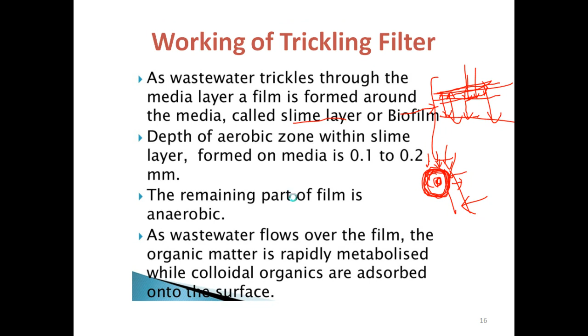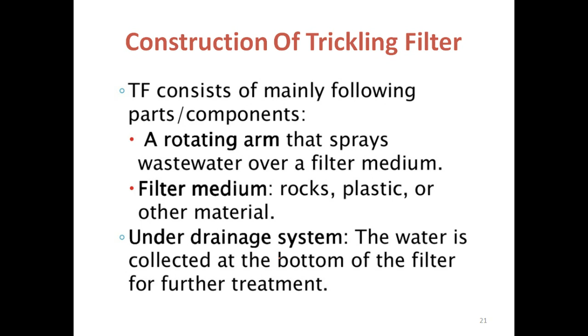One more thing in the working of the trickling filter: before passing water through the trickling filter, it should be passed through the primary sedimentation tank or skimming tank at least. Whatever organic materials in the wastewater can be removed through the skimming tank or primary sedimentation tank should be removed before the water is passed through the trickling filters. If not removed, they will clog the rotating arms, filter media or other equipment, or the under drainage system may be clogged by particles in the wastewater. So the removable particles should be removed in the skimming tank and primary sedimentation tank. Then the water is passed to the trickling filter for treatment.